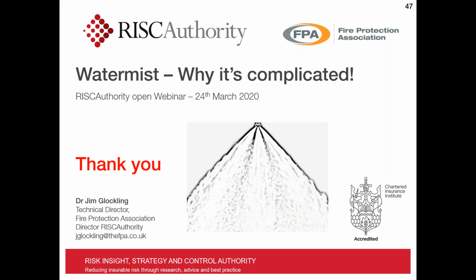So I think I will, actually I've got one more question which is coming. If used in a commercial kitchen, can the water mist heads be blocked by grease in the same way that fire suppression heads can be, and can they require a plastic cap? There is a very good new standard produced or certification scheme by BAFE for kitchen suppression systems, which I hope will take care of some of these issues to increase the likelihood of systems to operate in this sort of environment. Protection of the heads is obviously quite fundamental, particularly in the dirty environment of a greasy kitchen ducting network.